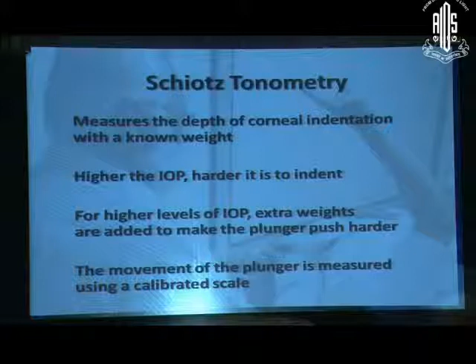Schiøtz tonometry, on the other hand, measures the depth of the corneal indentation with a known weight. Higher the IOP, harder it is to indent the cornea, and for higher IOP levels, extra weights are added to make the plunger push a little harder and get a little more sensitive. The movement of this plunger is measured using a calibrated scale. This is, in short, Schiøtz tonometry.